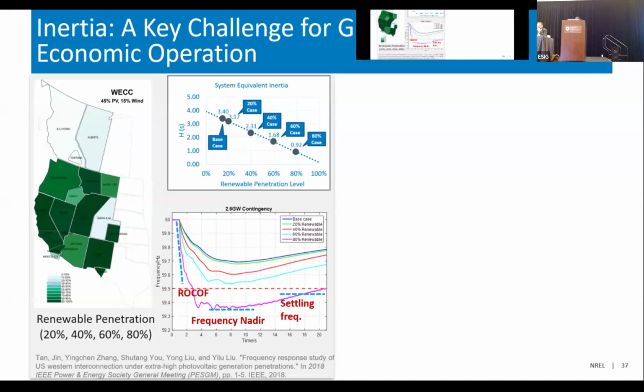I want to take the Western Interconnection as an example. As we push the renewable penetration level to 20%, 40%, even 80%, if you take a look at the upper figure, it shows that the inertia declined steadily. What does that mean? Even with the same contingencies, the largest N-1 contingencies for the WECC system, you'll get a faster drop of frequency, a lower nadir, a lower settling frequency, all pushing grid stability at risk.